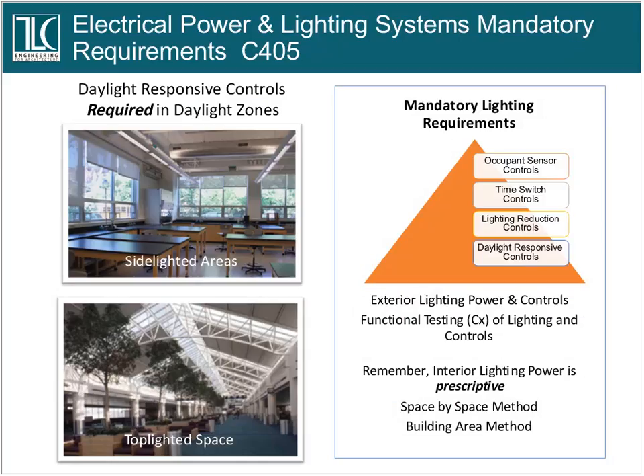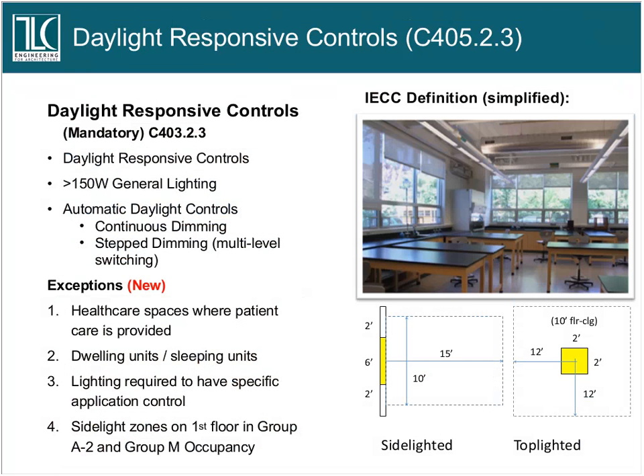Electrical lighting power, we've already seen that's gotten more restrictive. We've now got a whole lot more mandatory lighting controls: occupancy sensors, time switch, lighting reduction, where we have the ability to dim or shut off part of the light in a space, as well as these automatic daylight responsive controls. Once again, stuff that we've never had to do before. This is going to catch a lot of electrical designers by surprise. Spaces where they've not been doing daylight harvesting in the past, now mandatory. There's a few exceptions, but once again, any light that falls within this daylit zone is going to have automatic daylighting controls on it, stuff that we've never seen before.